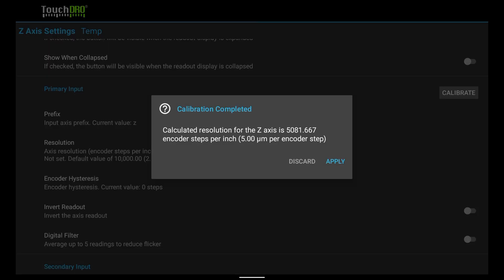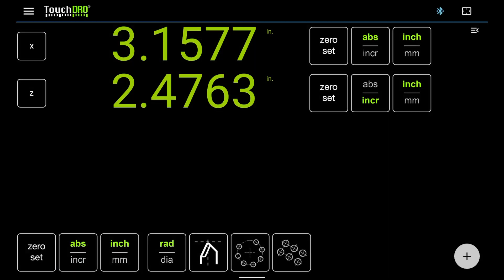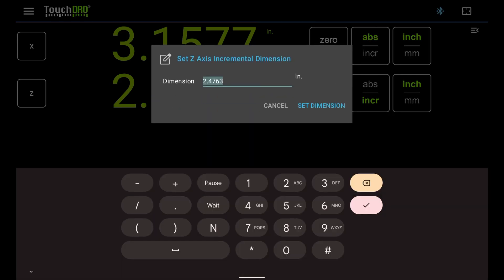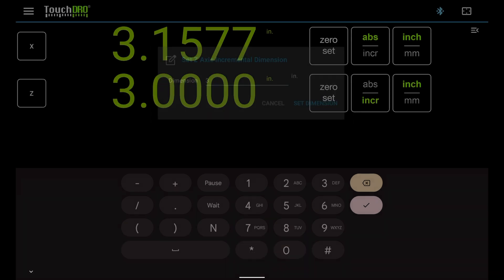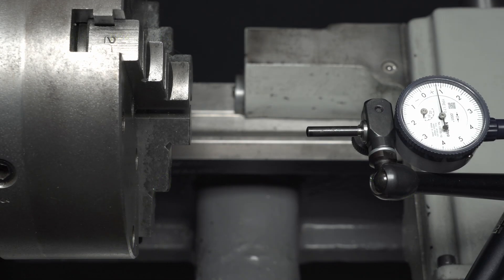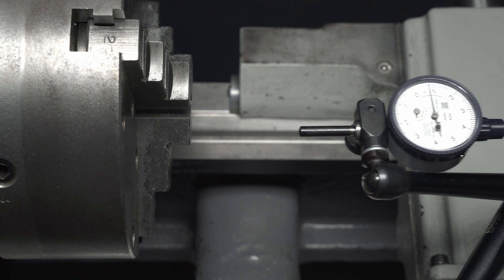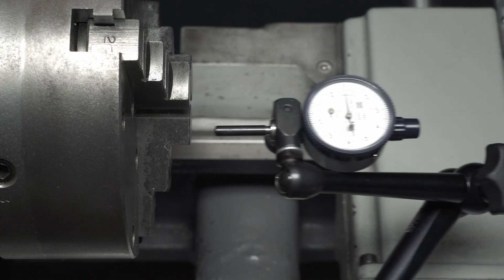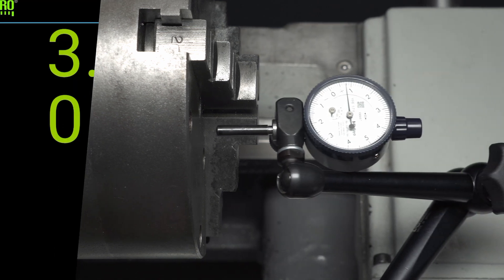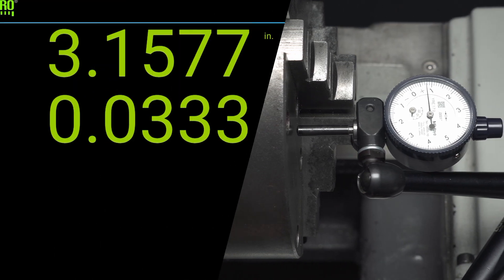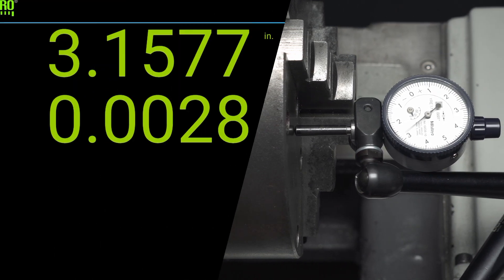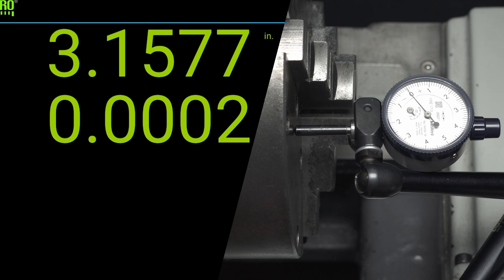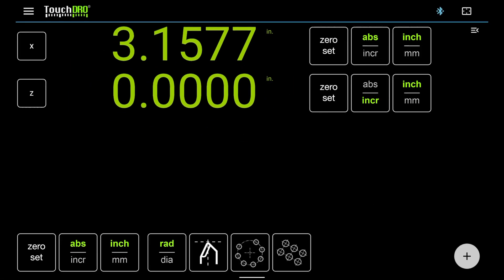This is a 5 micron scale, so the proposed resolution looks good. Tap apply and go back to the main screen. Let's check the calibration. Tap the z-readout. Enter the size of the calibration block and tap set dimension. The carriage should still be exactly 3 inches from zero, so we just need to move it back until the indicator reads zero against the chuck face. The readout returned to zero, so we have taken care of the linear error.